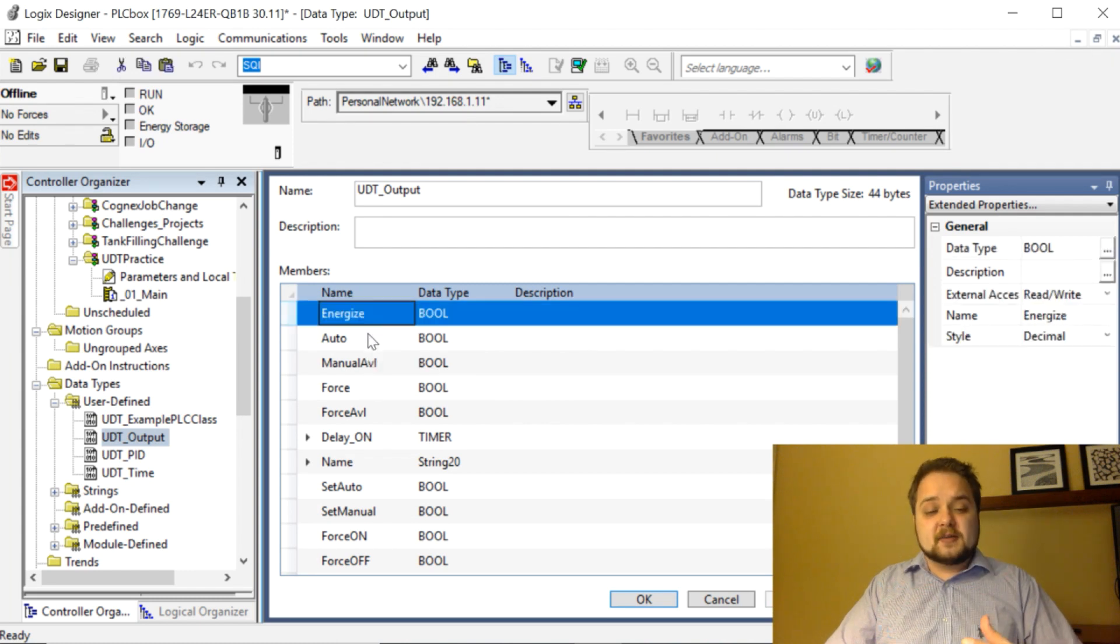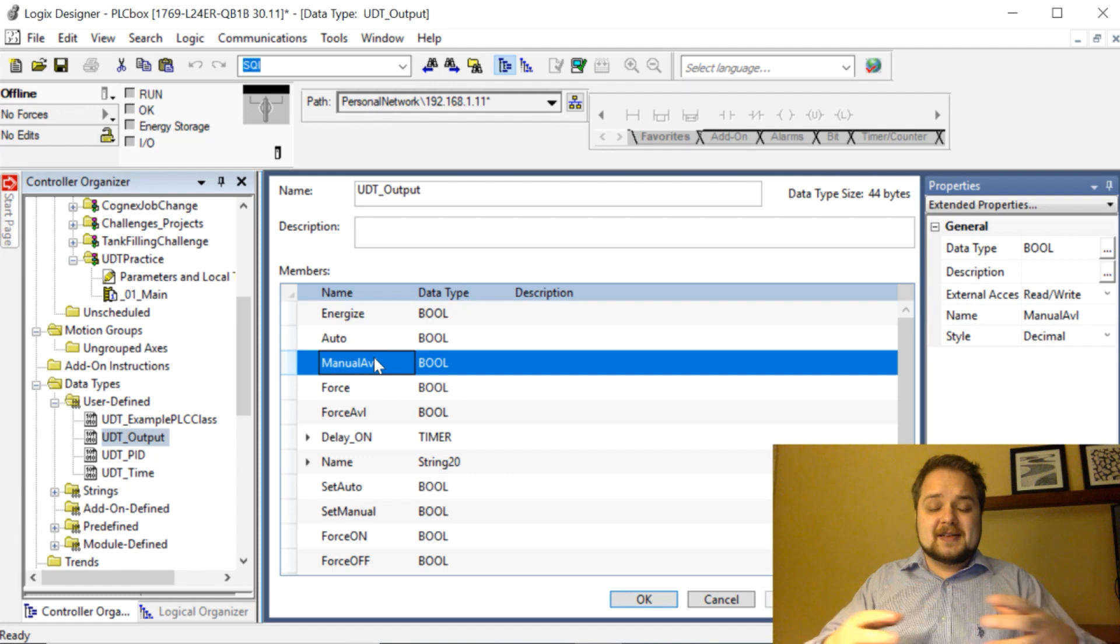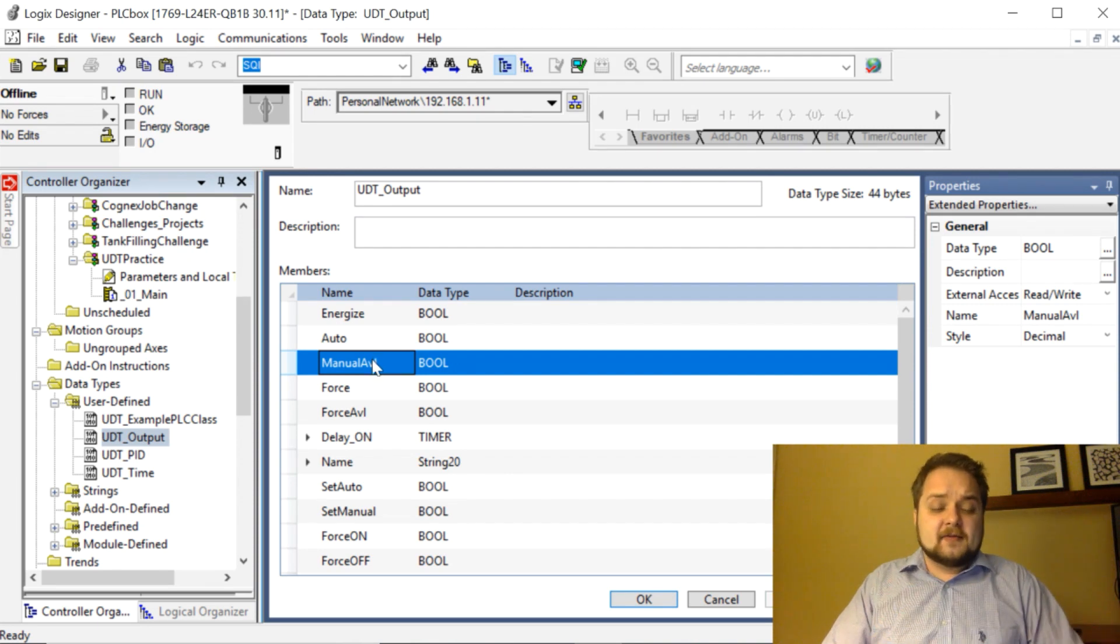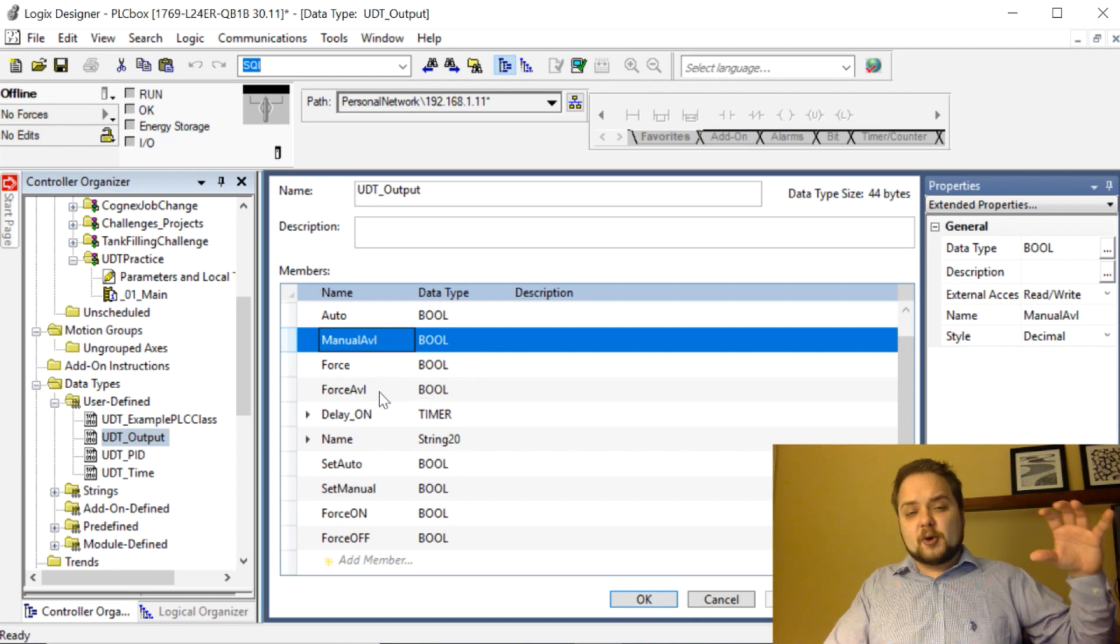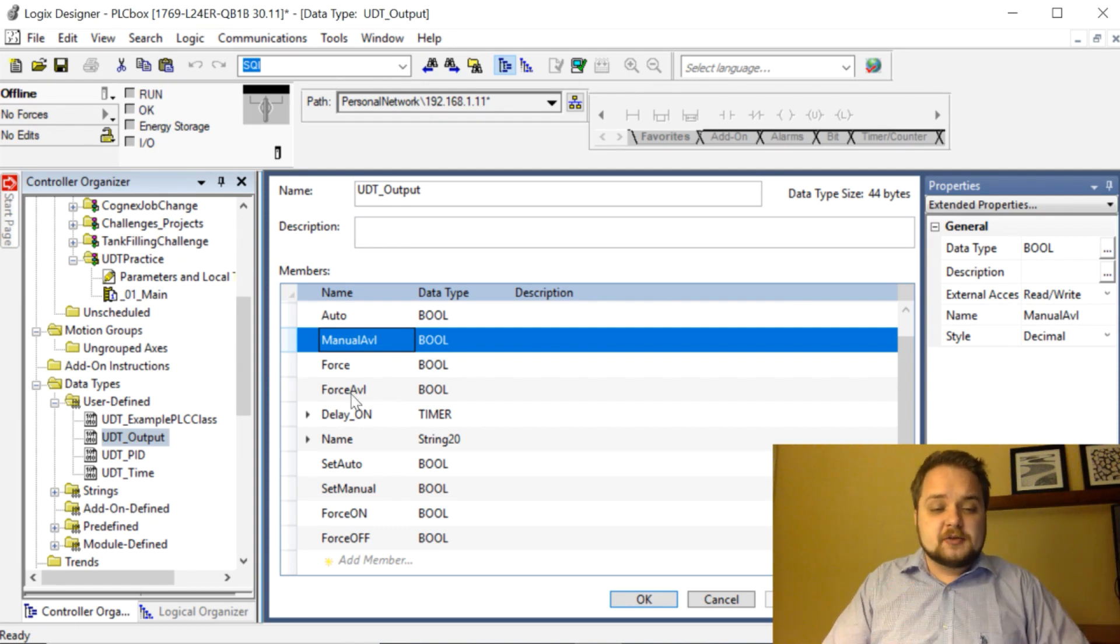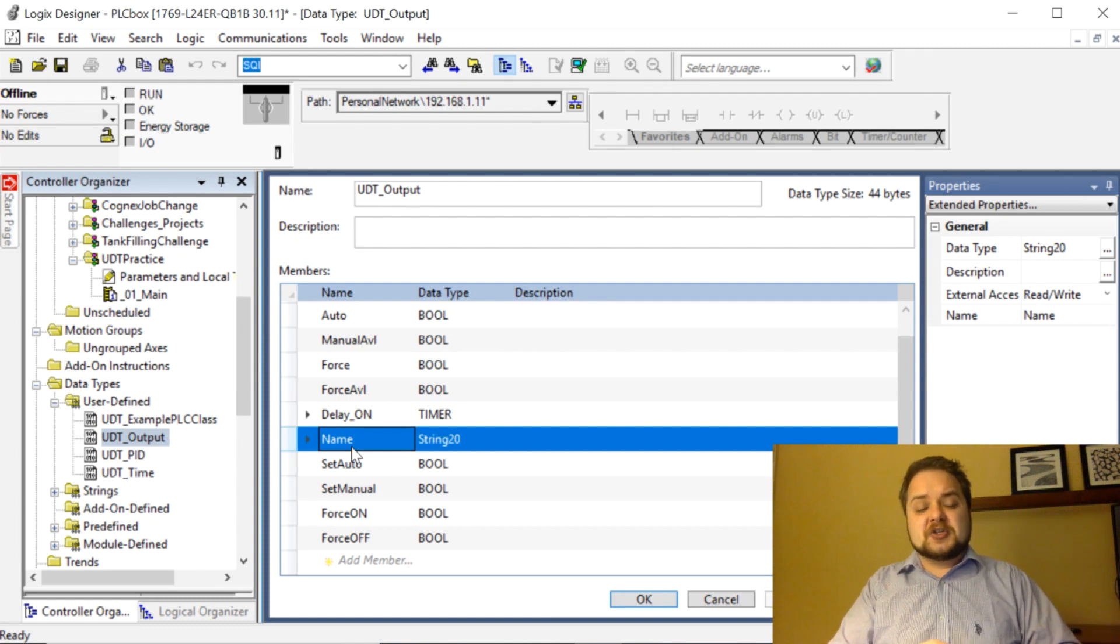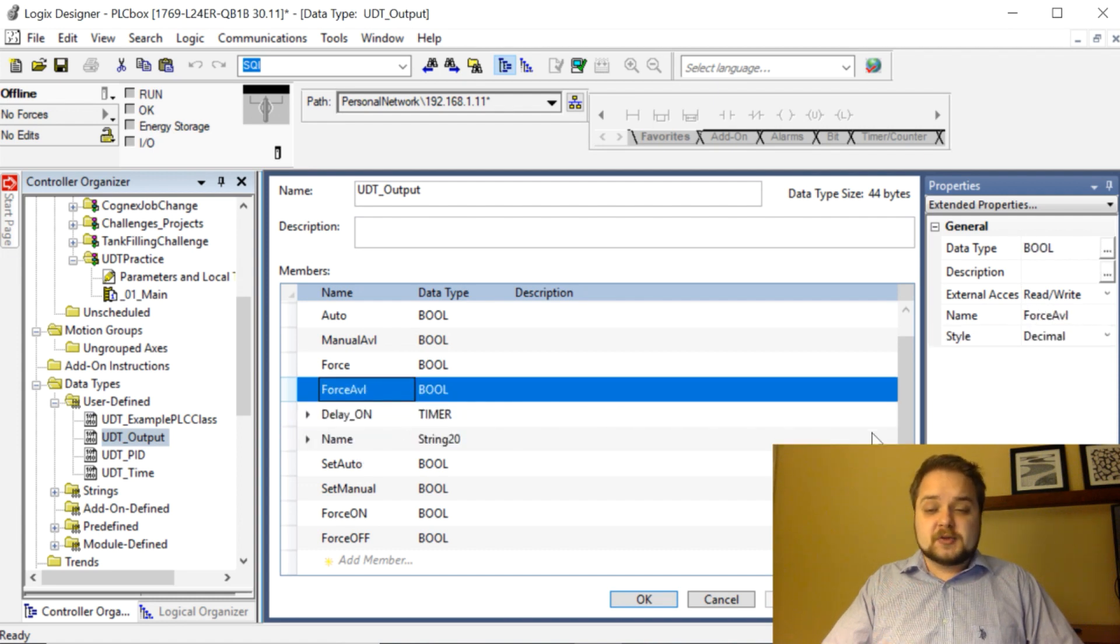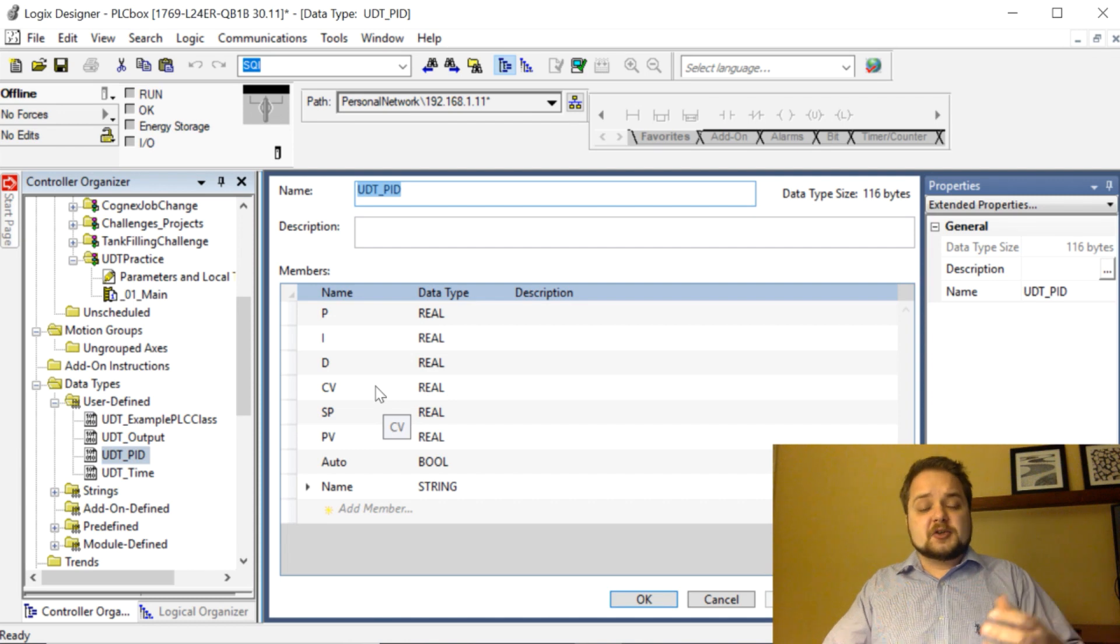Here we have an output structure, so an output, think of something simple that just comes on and off, but there are quite a few things that you can do within an output. Here for example an output can be energized, can be in auto, can be in manual. If you want full control of your outputs you can create a very simple yet powerful system that allows you to create the entire infrastructure for all of your outputs, and down the road essentially you can troubleshoot really easily. What this allowed me to do is to put a face plate on an HMI screen and allow the person to go into a manual function, something that for example somebody in maintenance would use and toggle the outputs or force the outputs from the screen on or off very securely. I also have this name which is going to be a string, so you can also combine that structure and give a name to your output so that your face plate on the HMI side can retrieve that specific unit and display the name of that particular output.